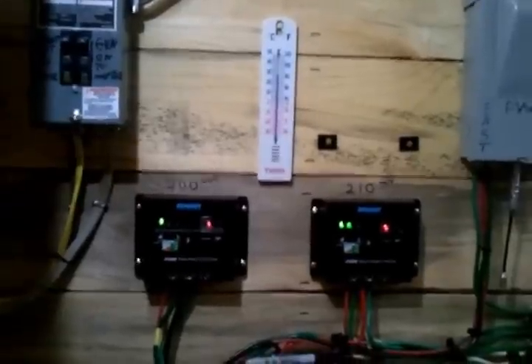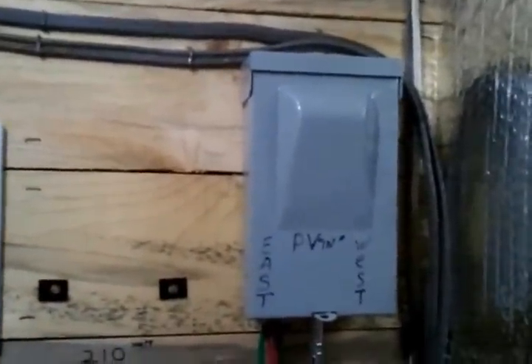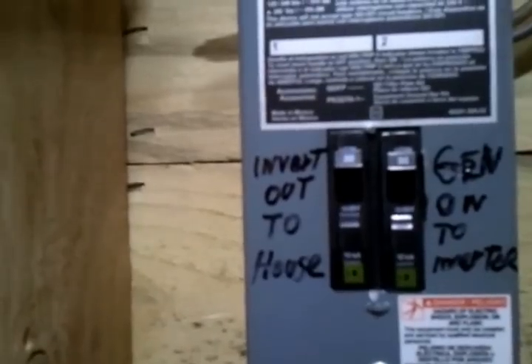There are two cheap PWM charge controllers — I don't have the money for an MPPT yet. I've got 610 watts on the roof of one of the buildings. This is a cheap way to do a disconnect — it was $11, with a pull-out type shunt. If you use the QO-style Square D breakers rated at low voltage, that whole box with bolt breakers was under $30. Another box goes to the batteries; this one is generator in and out to the inverter, house inverter out to house.